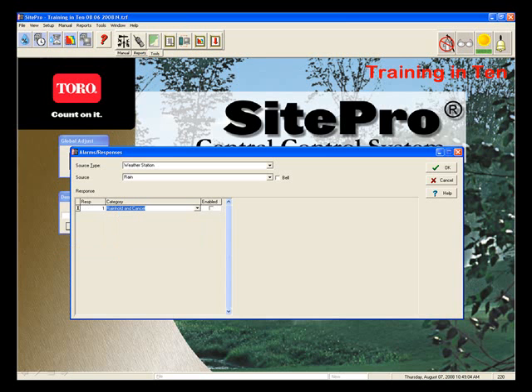So when we get a set amount of rain, the system will rain hold and cancel once we have placed a check in the bell log box to document it there, and we place a check in the enable box. Without these checks, the system will not document the alarm response. The final thing to do is to click OK to lock this alarm response in the system.